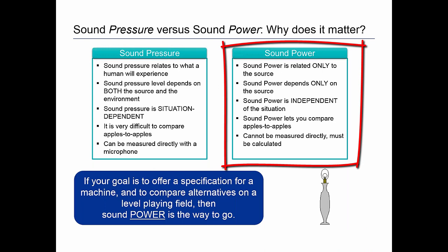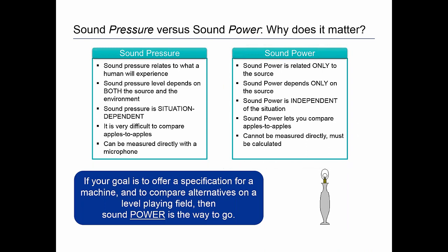Sound power is related only to the source that's emitting the sound. It depends only on the source — it's independent of the path or the situation in which the sound is being made. Therefore, sound power lets you compare apples to apples across different sources of sound, in this case different pieces of HVAC equipment. It cannot be measured directly like sound pressure can; it has to be calculated. So if your goal is to offer a specification for a machine or a unit and to compare alternatives on a level playing field, then sound power is the way to go.